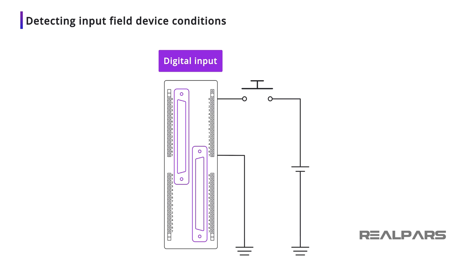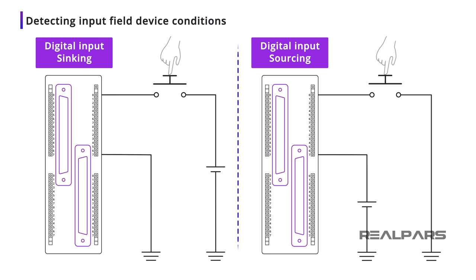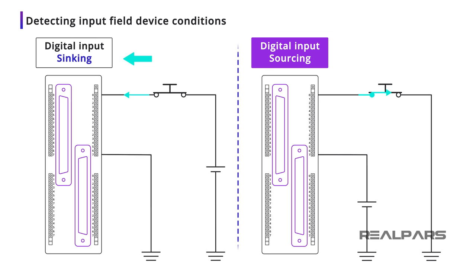Alright, now that we know how the digital input module determines the input device condition, let's talk about the current flow between the power supply and the input module. There is a current flow, but it is very small and usually under 10 milliamps. Notice in our example that the current is flowing into the PLC module. Depending on the type of PLC input module and how it's connected with the input device, the current could flow in or out of the module — that's where the terms sinking and sourcing come into the picture.